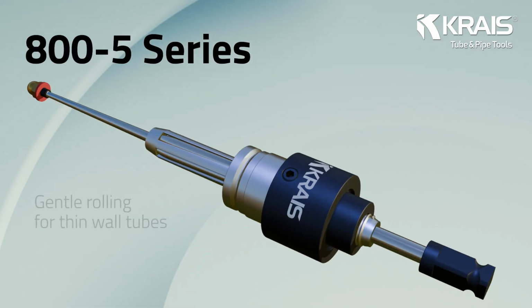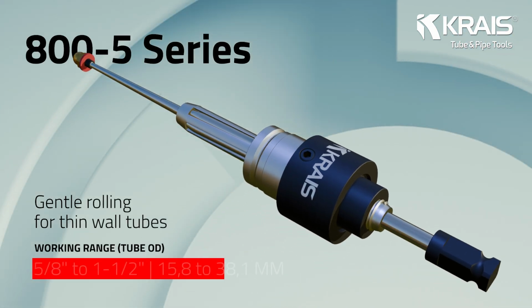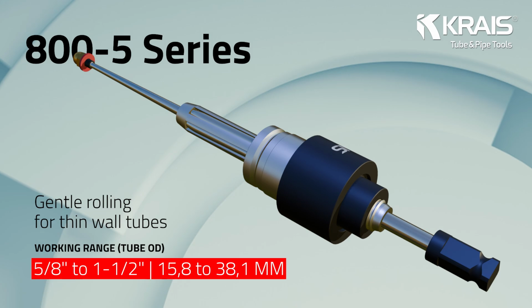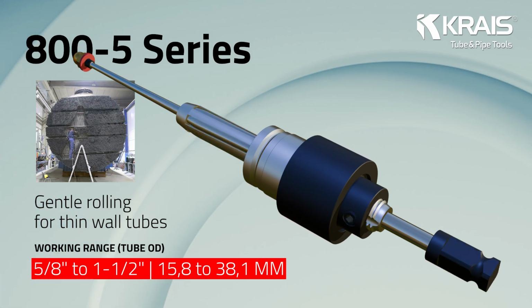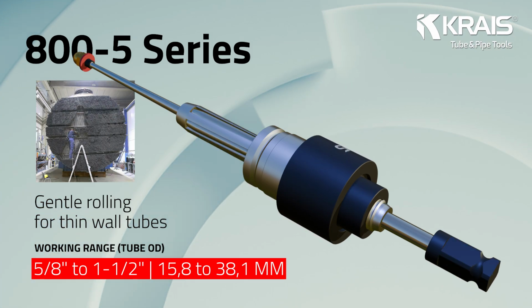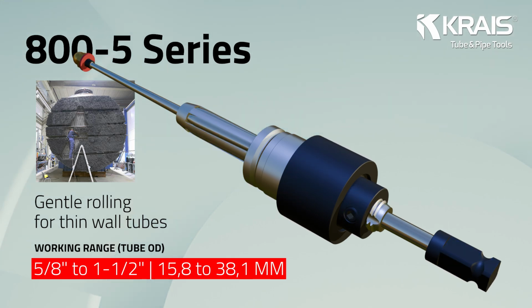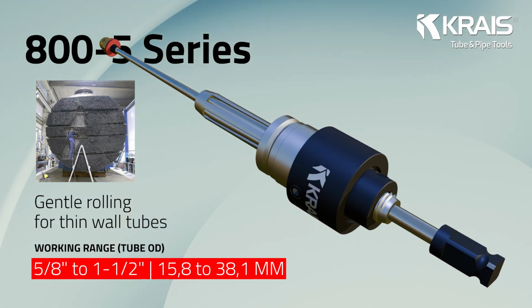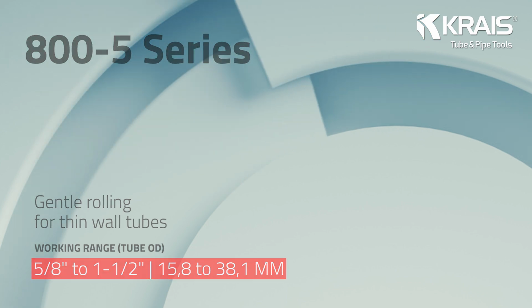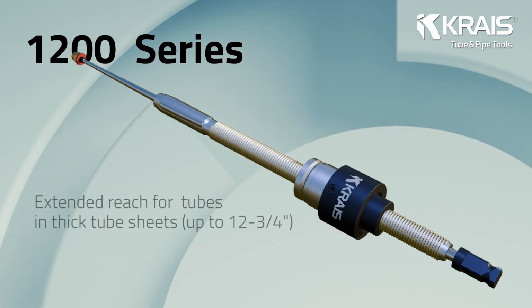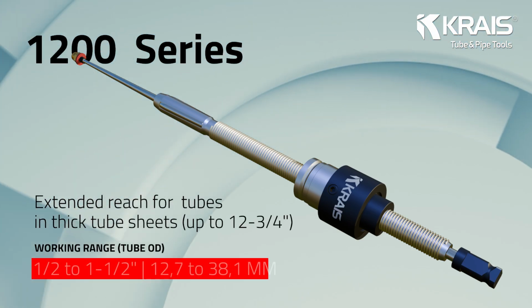The KRAIS 805 is the 5 rolls series designed for thin wall tubes and tubes that are more sensitive to deformation. 5 rolls distribute forming forces more evenly, reducing the risk of ovality and local distortion, particularly in very thin wall tubing.